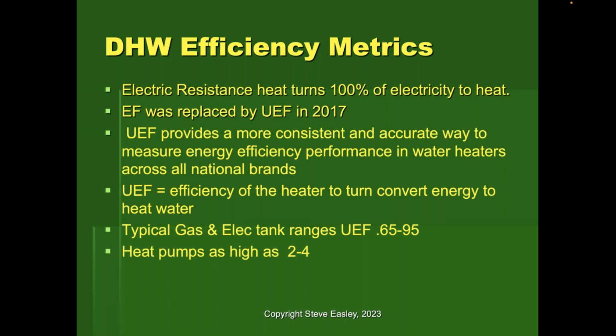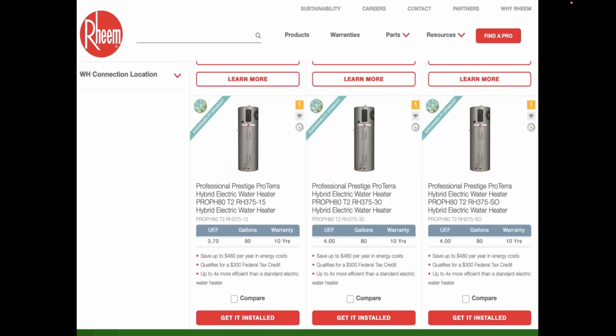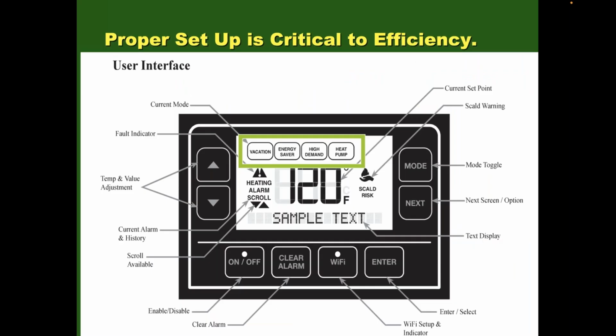It simply provides a more consistent, accurate way to measure the efficiency and performance of water heaters across all brands. UEF, basically, the higher the number, the better it is. It's the efficiency of the water heater to convert energy into hot water. And then, of course, typical gas and electric UEF ranges for standard equipment are between .65 and .95. Heat pumps can be between 2 and 4. So obviously, heat pump water heaters are much more efficient. You can go online and look at a variety of these. This is what I installed. It has a UEF of 4, so it's pretty efficient. I know it looks similar to a COP, slightly different, but close enough. And then it's important to recognize that setting these up correctly matters, because if you run this on high demand all the time, your customers won't see any savings. In fact, you might even see more energy use.